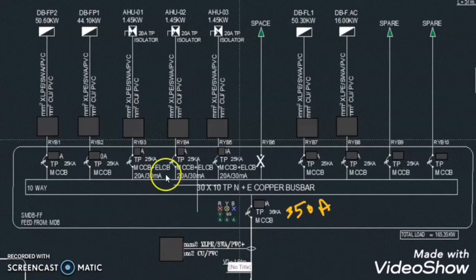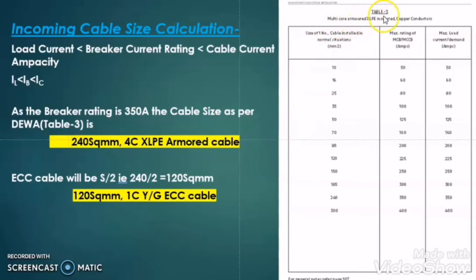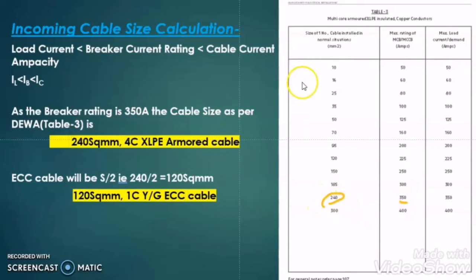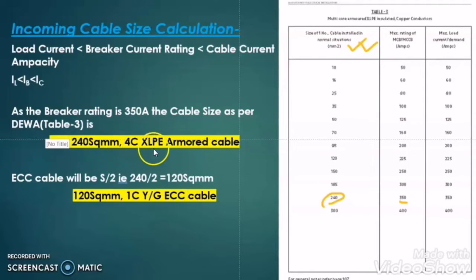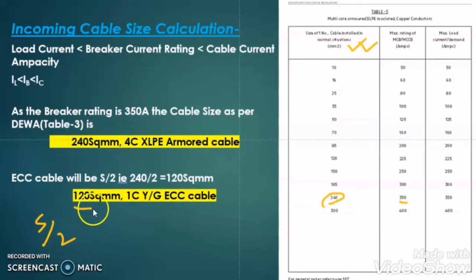Now let us calculate what would be the cable size for this SMDB. In order to get the incoming cable size we have to refer to the DEWA table number 3 for multi-core armored XLPE insulated copper conductor. Here you see that when the MCCB rating is 350 Ampere, we have to go for 240 square mm multi-core cable. So as per this table, the cable for this SMDB is 240 sq mm 4-core XLPE armored cable. And as per the same DEWA regulation, if the armored cable phase cable is 240 then the ECC cable required is S ÷ 2, that is 240 ÷ 2 = 120 sq mm.